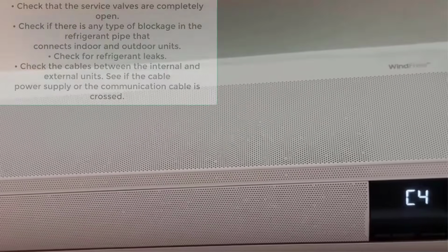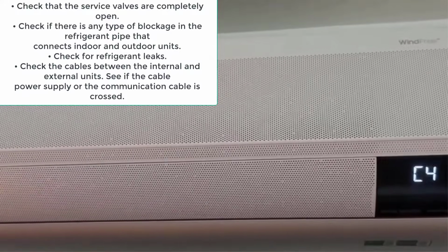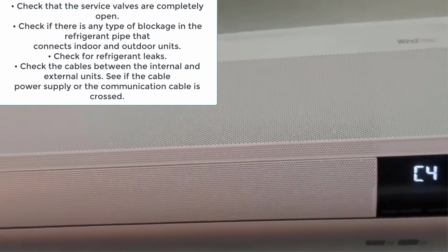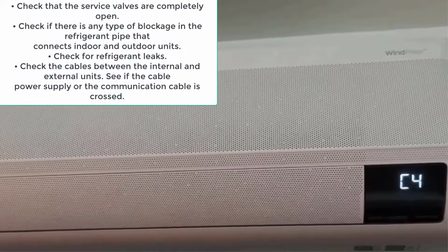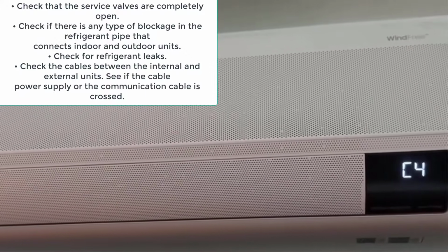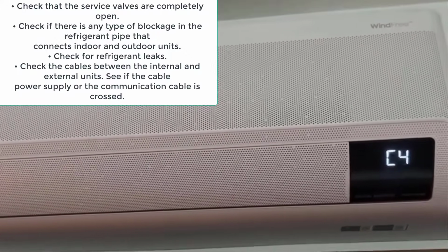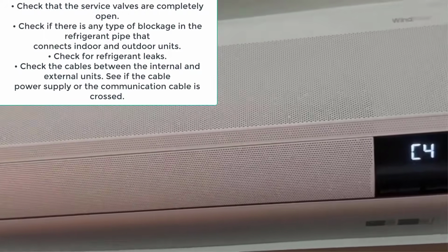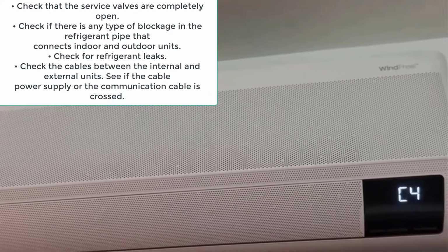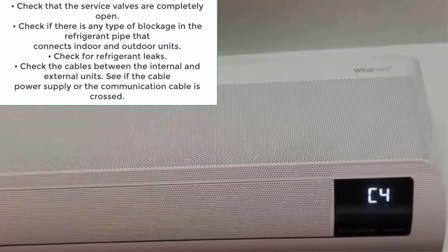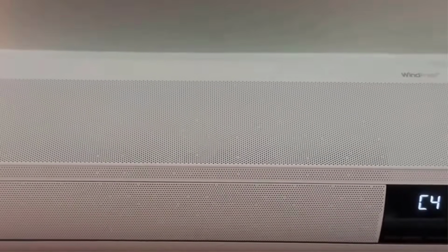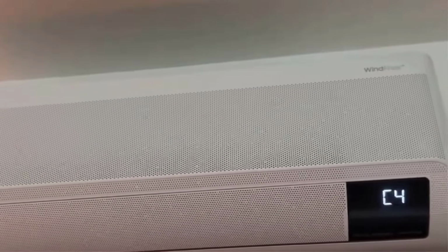First, check that the service valves are fully open. Then check for any blockages in the pipe connecting the indoor and outdoor units. It's also important to check for refrigerant leaks. Finally, check the communication cables between the indoor and outdoor units, making sure that the power cable or communication cable is not crossed. Now about how the error appears on the display.